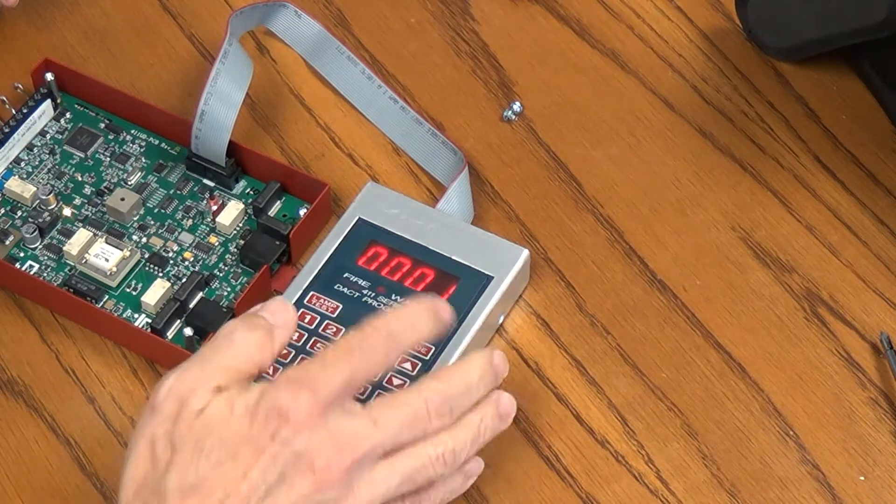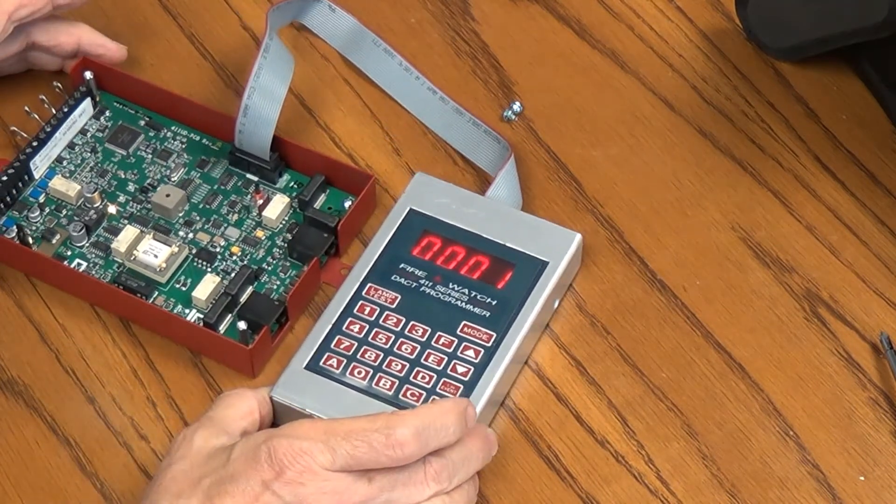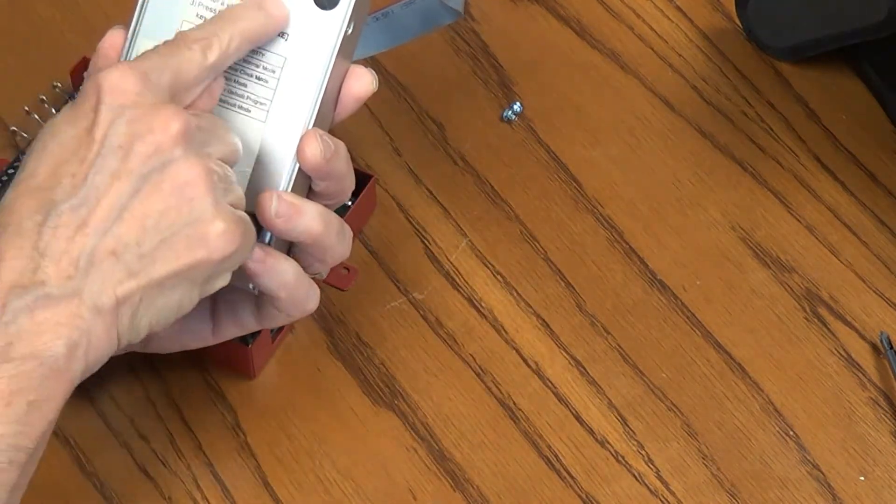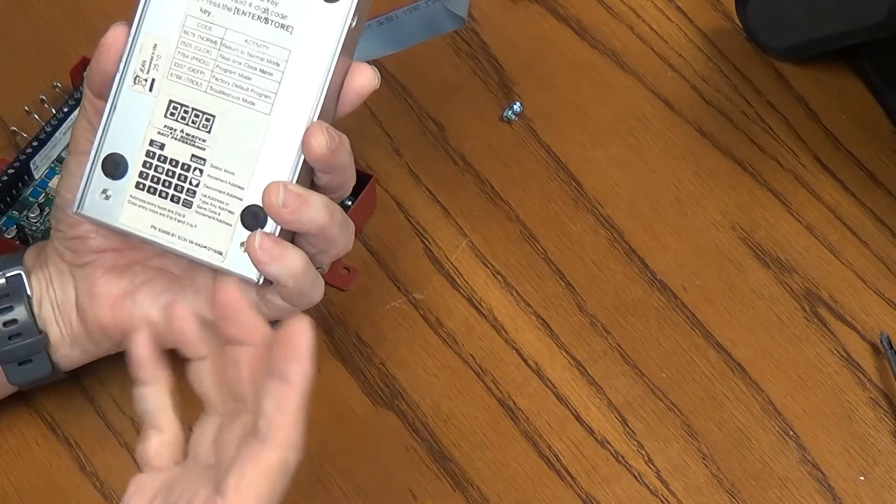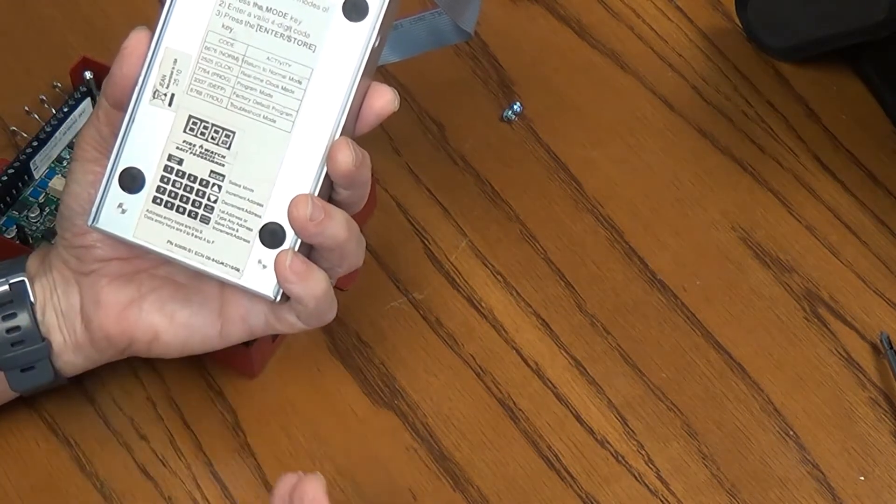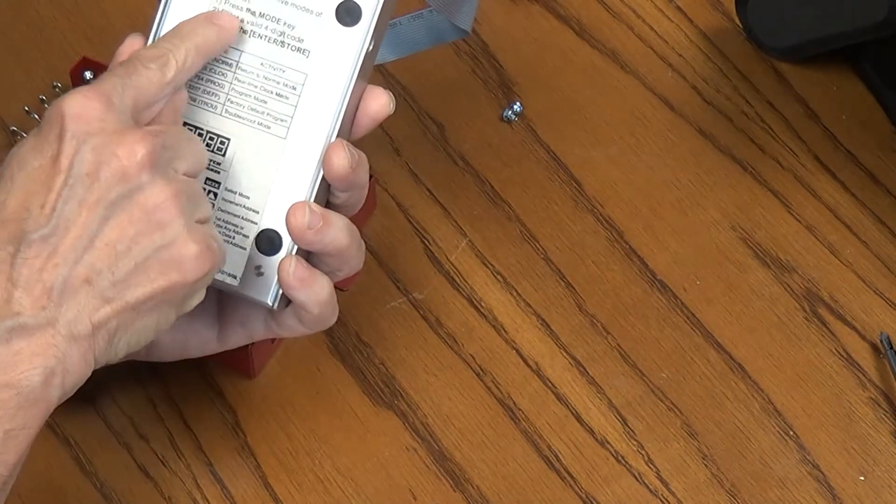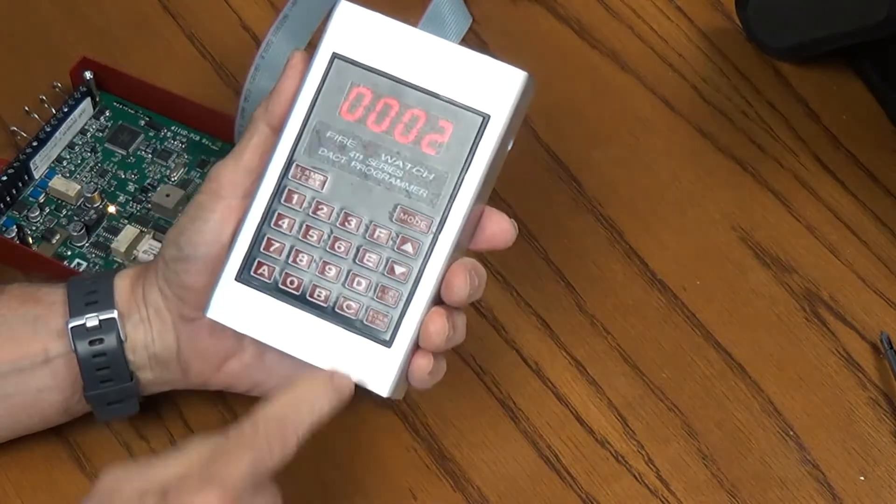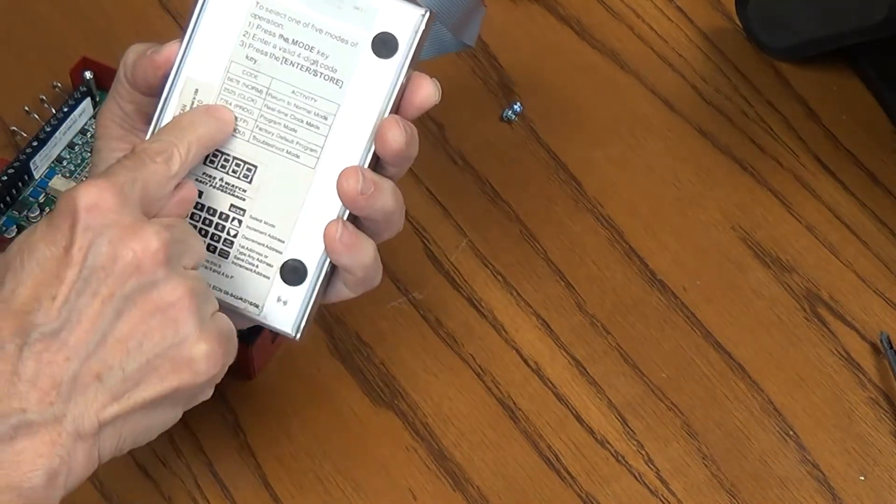Now you'll notice that the 411 programmer is lit up. Now we can use this to start programming the 411 dialer. There are instructions on the back of this. Basically it says there's five modes of operation. We're going to use two today. One is program, which will put the card into programming mode so we'll be able to actually configure it. And then there's normal, which will end that programming and bring it back to normal operating. It says press the mode key, enter a valid four digit code, and then press enter store. To program, it's 7764.